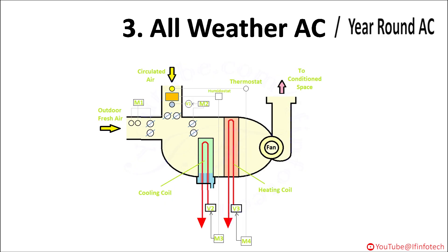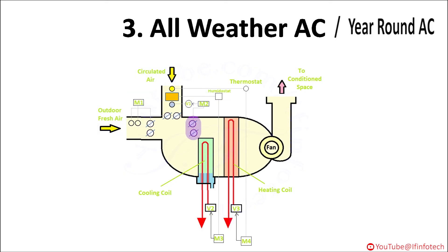In all weather AC, the amount of outdoor fresh air and recirculated air is controlled by motor M1 and M2. The air conditioner is designed such that when outdoor air temperature is either above or below a certain selected value, it is assumed to be summer or winter season. In summer season, the bypass damper is almost closed and most of the air passes through the cooling coil. The cooling coil may be an evaporator coil or a coil through which chilled water is passed. It is provided with valve V2 which can be controlled by motor M3.